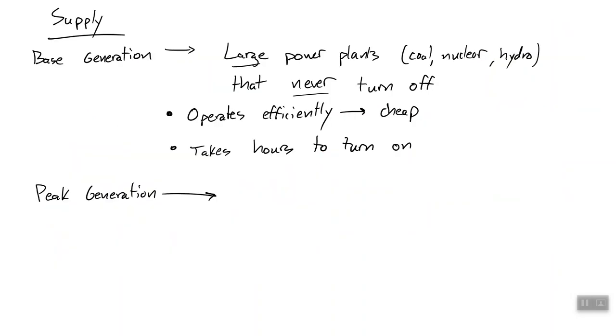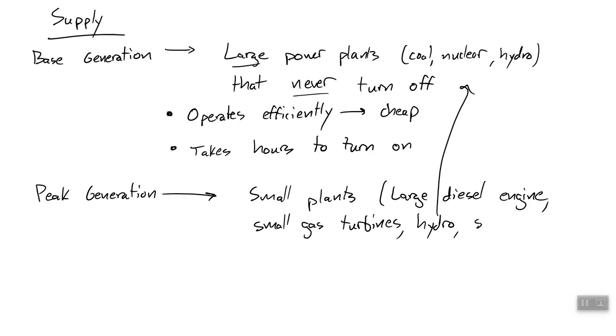And so we have peak generation facilities, which are small power plants, things like very large diesel engines, think like the giant engine on an aircraft carrier strapped to the ground. Or small gas turbines, things that aren't combined cycle, but just a single gas turbine, less efficient, easier to turn on. Hydro, even though it's kind of a large plant, you can turn it on and off fairly easily and quickly. Then also energy storage, which you can bring online really fast.